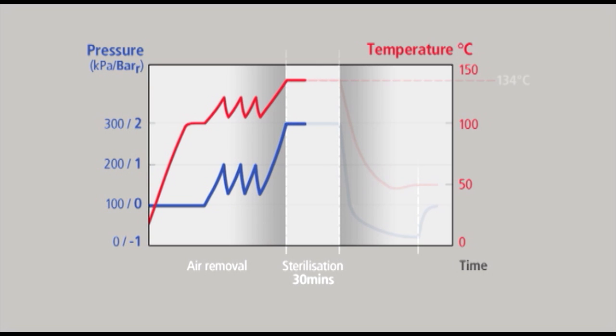The system works by first heating water to produce steam. Air removal from the chamber and load is carried out by three pulses of steam. Sterilisation of general hospital loads takes 30 minutes at 134 degrees Celsius. This is followed by a drying phase by vacuum for 30 minutes.